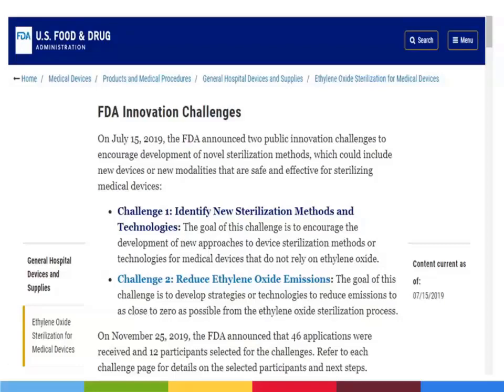Having said that, they give it to the engineer, and they tell the engineer, come up with the best method of doing this, and please do it quickly because we'd like to get to market. So the testing is done in-house, and then those reports are provided to the FDA. And so what the FDA then does, it reviews those reports and says, that's adequate, you got a 6-log drop, so we're going to approve this process of sterilization for this particular supply. I've been told there's some 60,000 different types of products out there. So there are many, many different approvals here.